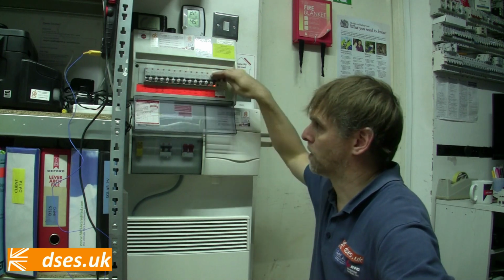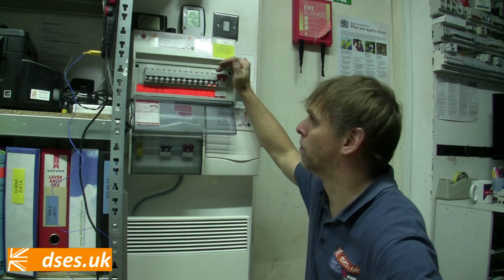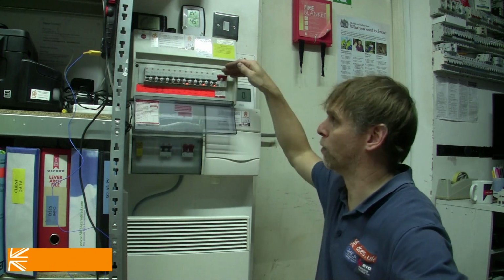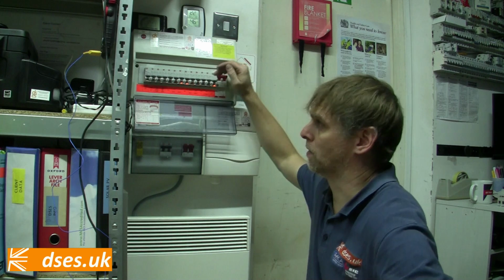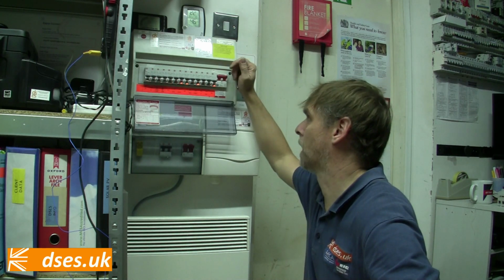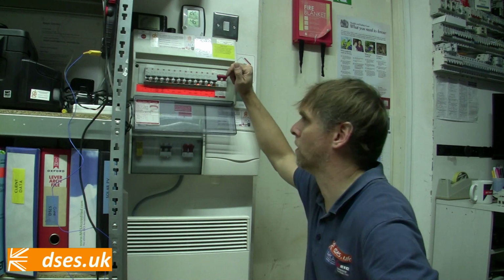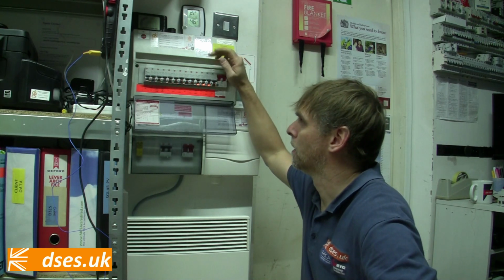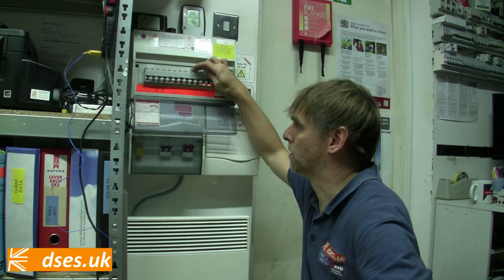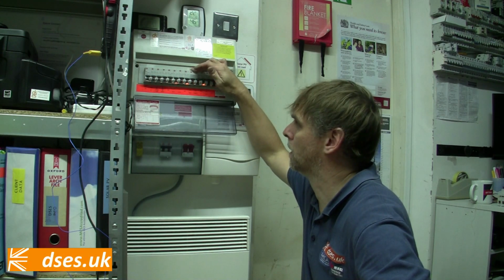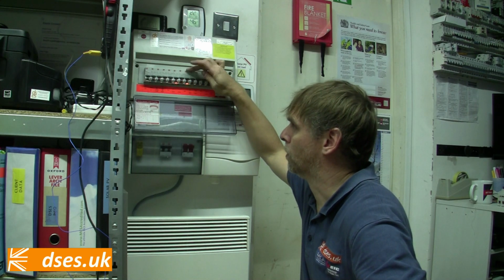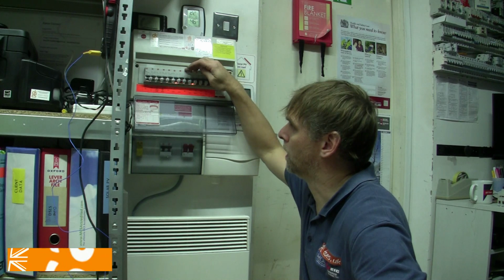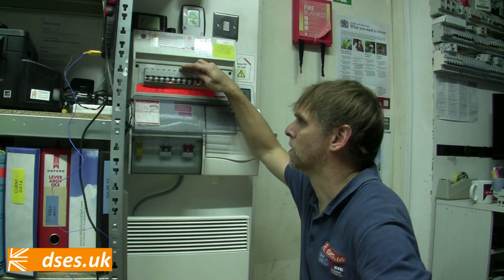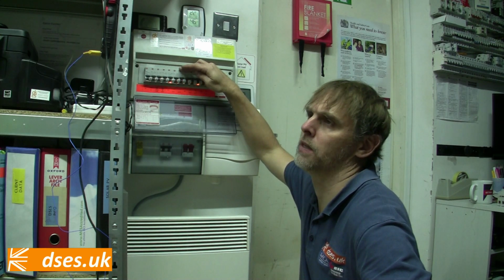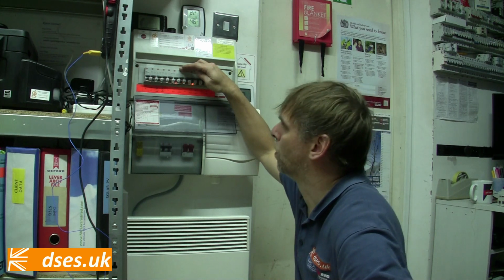These aren't arranged in order of size, they're arranged in order of where the cables were inside the board. Obviously there's no point extending a cable to bring it over here just to keep the breaker in size order. The busbar is capable of carrying 100 amps, it's a 60 amp supply anyway, so it doesn't really matter if I've mixed them around a bit. The original house socket ring, the office socket ring, and yes, they are rings here, I didn't put them in. The induction hob, the upstairs heating, that's something that went in after I got rid of the gas system. So there's a couple, I think one underfloor heating solution up there and some panel rads, all hanging off a 20 amp breaker.